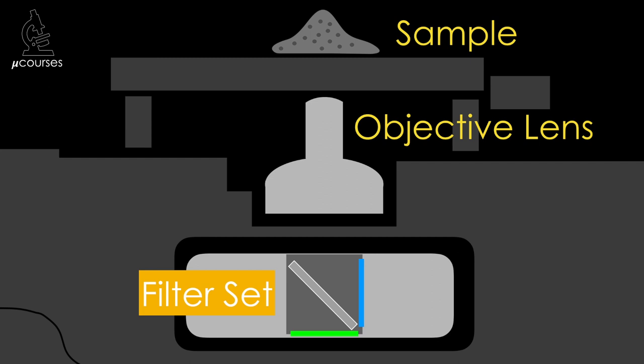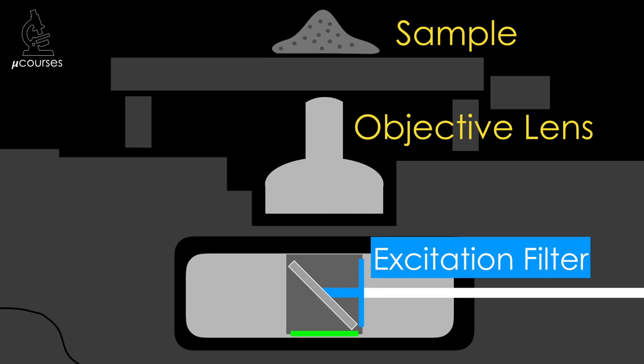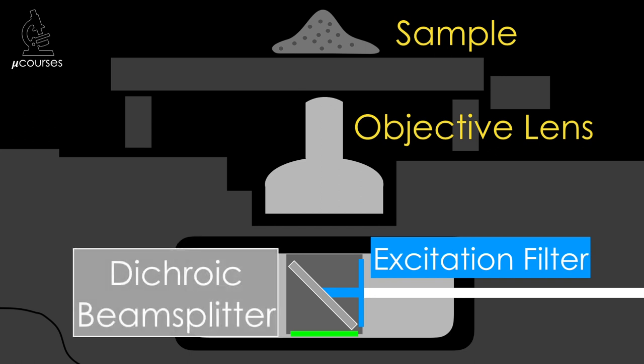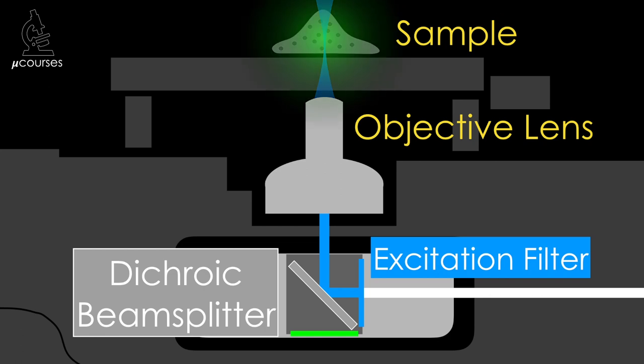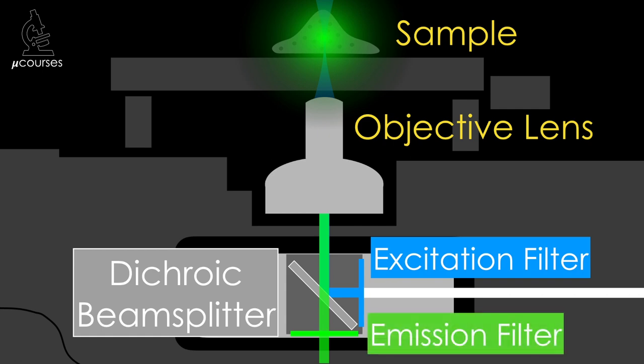The filter set is made up of three optical elements. Light from the light source hits the excitation filter, which allows through a range of wavelengths to excite the sample. This excitation light then hits the dichroic beam splitter, which reflects the excitation wavelengths through the objective lens to the sample. The sample absorbs the light and emits longer wavelengths which, if collected by the objective lens, pass back to the dichroic beam splitter. The dichroic beam splitter is designed to allow the longer emission wavelengths to pass through to the emission filter.